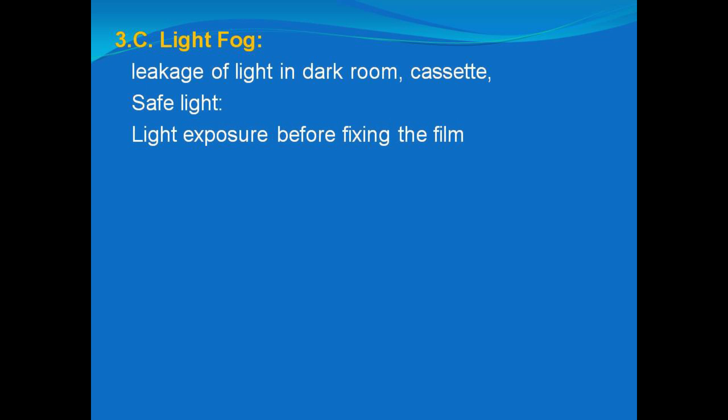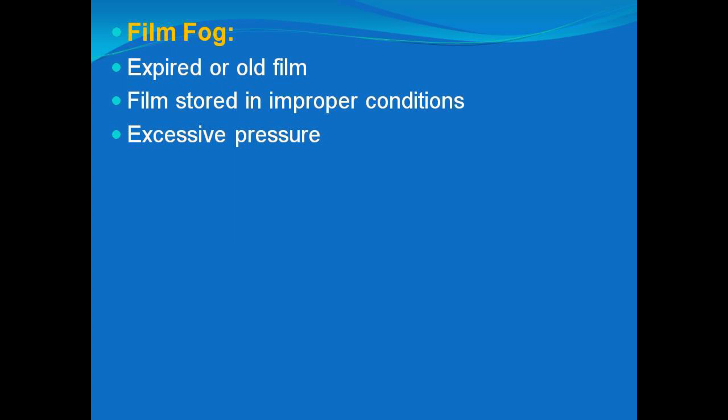Light fog can be due to leakage of light in the dark room, leakage in the cassette, the intensity of the safe light being too high, or the film being exposed to light before it is exposed by x-rays. Film fog results when we are using very old or expired film.